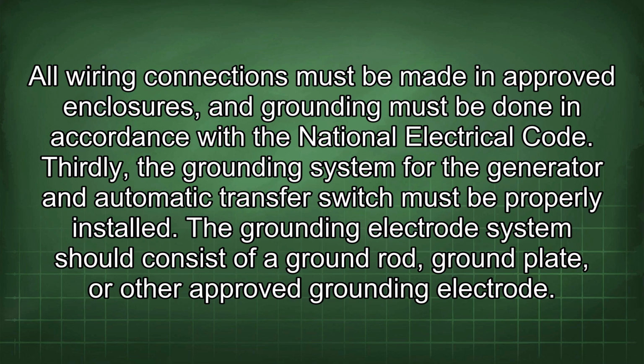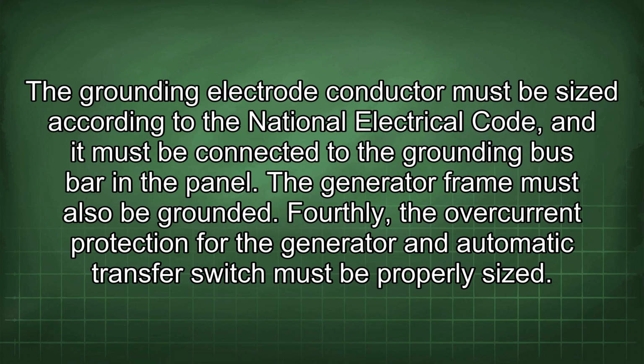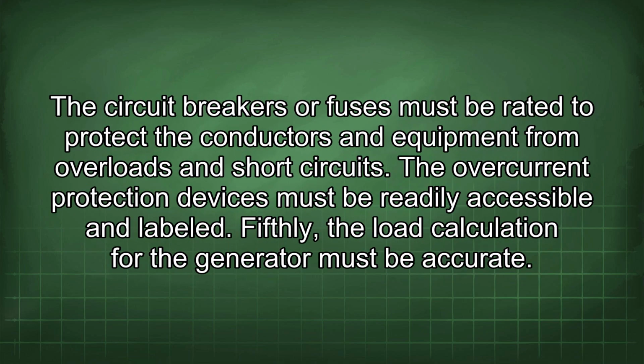The grounding electrode system should consist of a ground rod, ground plate, or other approved grounding electrode. The grounding electrode conductor must be sized according to the National Electrical Code, and it must be connected to the grounding bus bar in the panel. The generator frame must also be grounded. Fourthly, the overcurrent protection for the generator and automatic transfer switch must be properly sized. The circuit breakers or fuses must be rated to protect the conductors and equipment from overloads and short circuits. The overcurrent protection devices must be readily accessible and labeled.